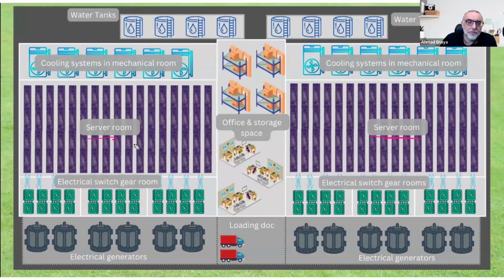In case of any big failure, we need to make sure every room has its own cooling system, its own switchgear power system, its own generators, its own loading dock, and even its own water tanks for the cooling system. So every room should have its own independent systems.